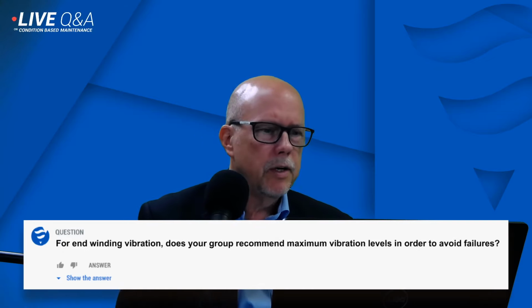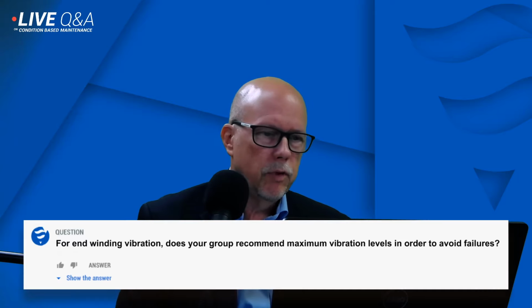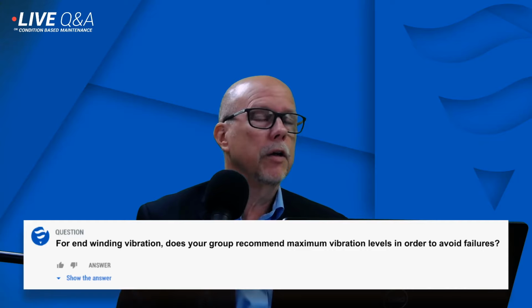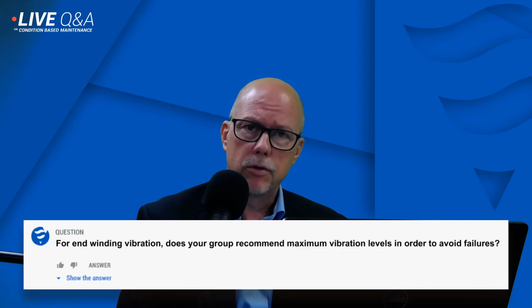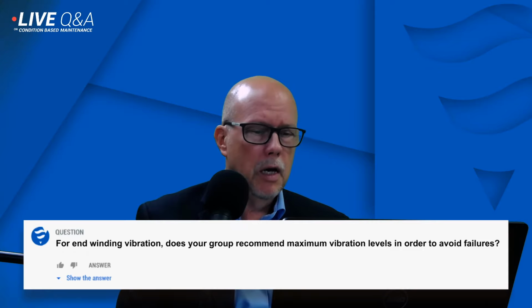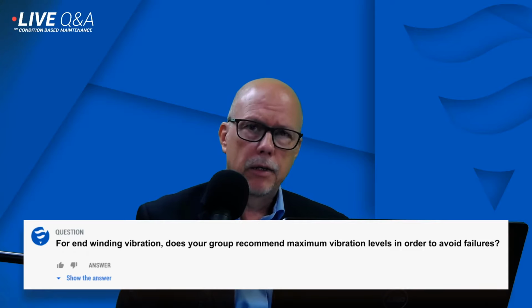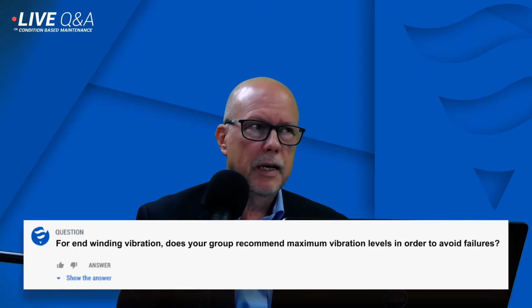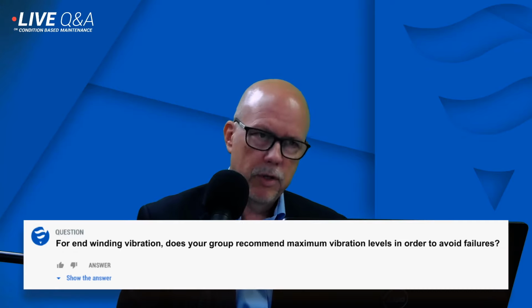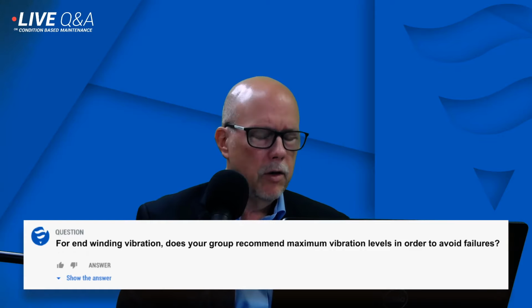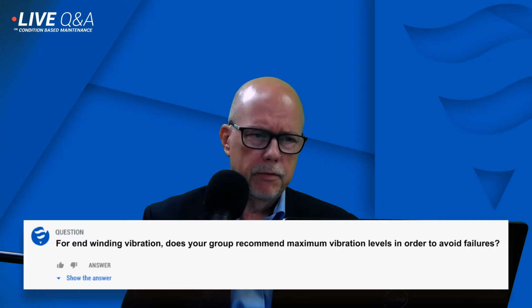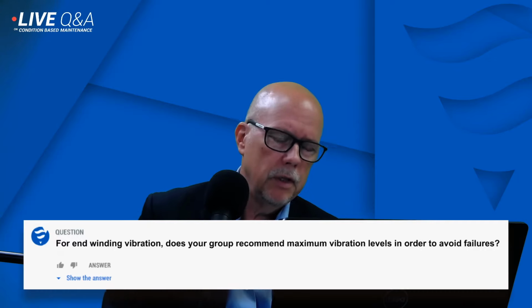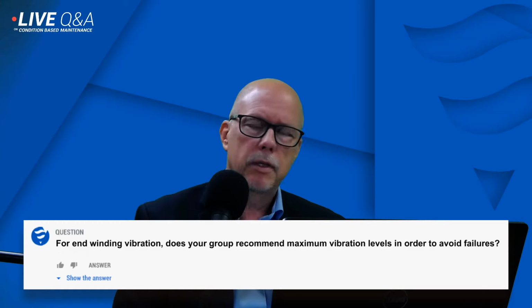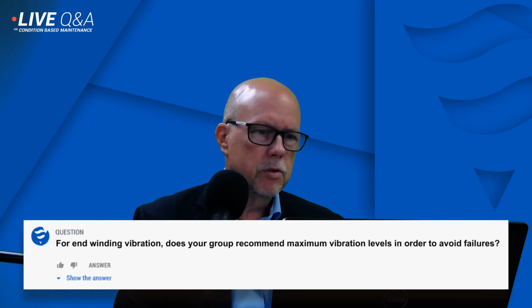Another question, end winding vibration. Does your group recommend maximum vibration levels in order to avoid failures? Yes, we do. Unfortunately, there are no international standards for end winding vibration. IEEE came out with a document on end winding vibration, but they had numbers that were simply suggestions. They were not actual tolerances. I also participated in a committee for IEC briefly, because during the meetings they mentioned that there would be no tolerances in the document. So I felt this is not necessary to continue to participate.